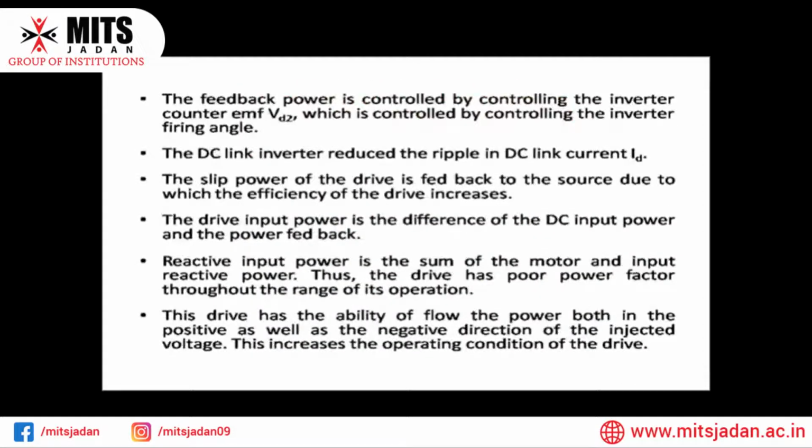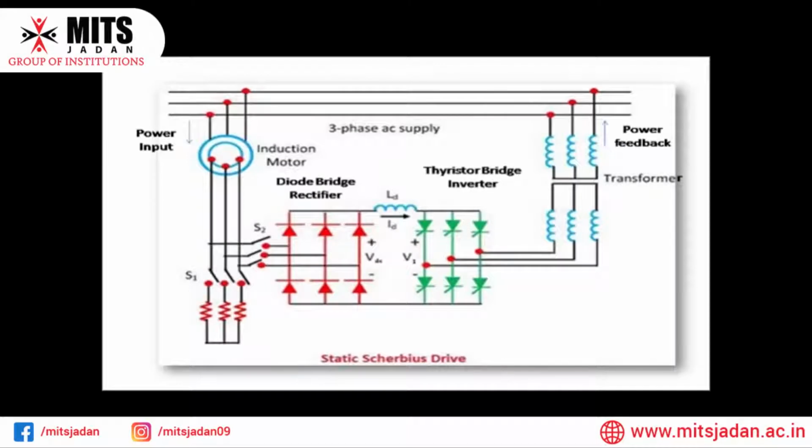So here we can see the circuit diagram of the static Scherbius drive. Here is an induction motor, and that is getting the three-phase AC supply, and here is a diode bridge rectifier circuit, and on this side we have a thyristor bridge inverter circuit, and with the help of the transformer the power is fed back to the AC supply.